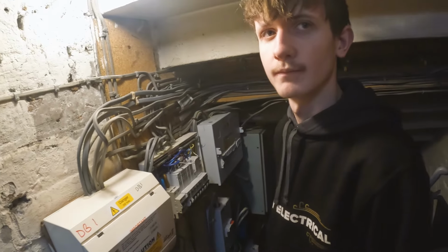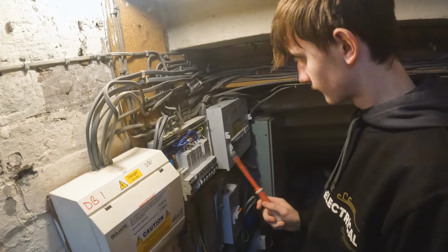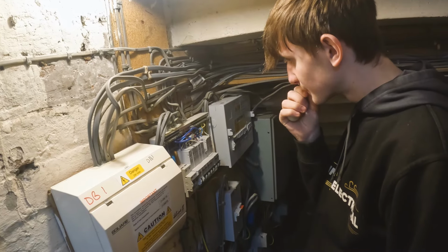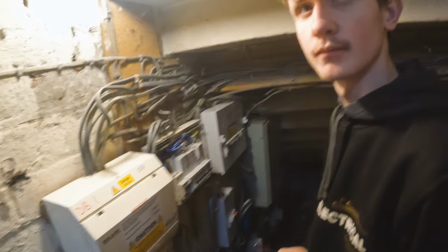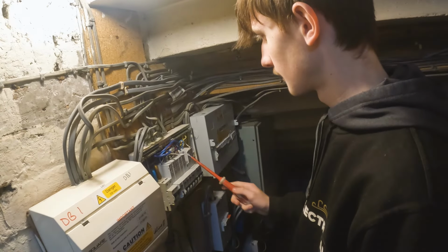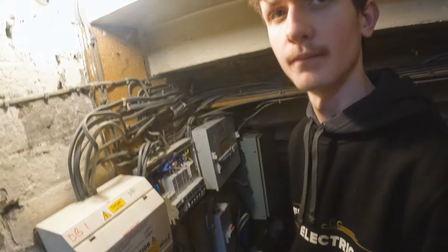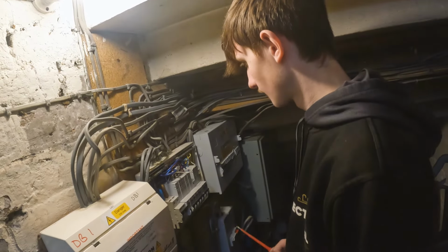Disconnect the neutrals? Do you think we'd take the lines out and the neutrals out? Yeah, figure out which line is for which neutral and power out one of the circuits. Or you could test both and see which is the bad one, if you want to do it dead. I say test both. Yeah, let's test both then.